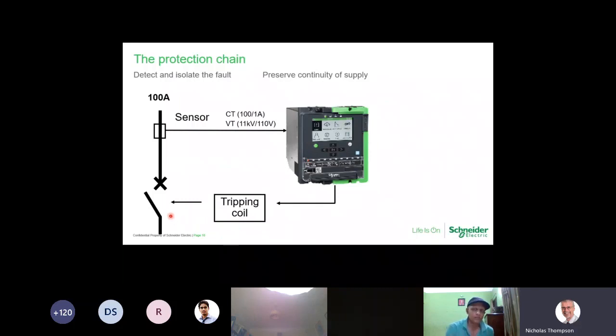So our trip coil is embedded inside the circuit breaker. It is the mechanical means to release the stored energy of the springs when the circuit breaker is closed. So any one of that chain can fail, and there are supervisory circuits that are built into the protection relay, and you can have an additional relay which will supervise the whole protection chain, right from your CT through to your relay, through to your trip coil, through to the actual circuit breaker and the position of the circuit breaker. So when we have got our circuit breaker closed on a healthy circuit, everything's hunky-dory. It's supplying information back through to the protection relay. That protection relay is constantly monitoring, and it's constantly looking out for information coming back from the sensors as to what's going on with the network.